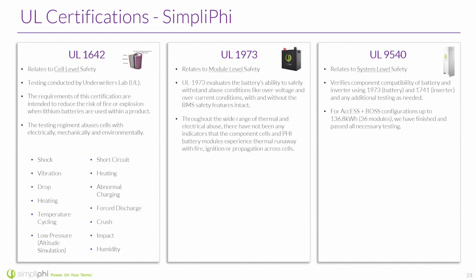And then the most recent, UL 9540, relates to system level safety. This has been popping up all over the place, so you're going to see more and more jurisdictions looking for that UL 9540. We do have numerous products, like our Access line, that are approved for UL 9540, and that testing we have completed.